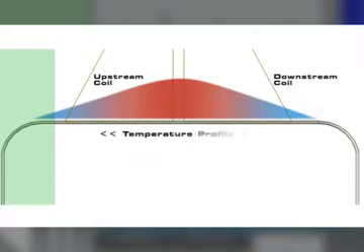The sensor is a very small tube called a capillary. The 316 stainless steel tube is precisely wound with two platinum wire coils and heated to form a pair of resistance temperature detectors known as RTDs. When there is no gas flowing, the capillary tube temperature profile looks like this, even and balanced, hotter in the middle and cooler on the ends.